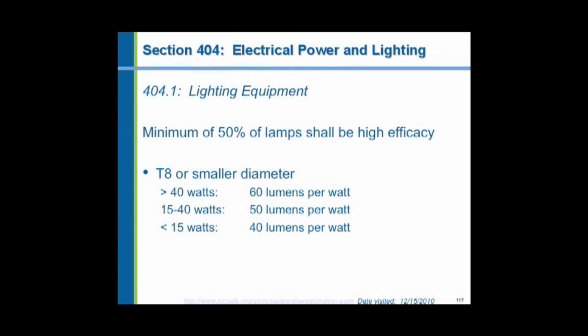And the lamps also have to be T8 or smaller in diameter. The designation of a fluorescent lamp, the number means the diameter of the tube in eighths of an inch. The fluorescent tubes that we've had for decades have been T12s. That means 12/8 of an inch, or 1.5 inches in diameter. T8 means they're 1 inch in diameter. So the new energy code requires that we use high efficiency lamps, high efficacy at the various sizes, in the T8 style.